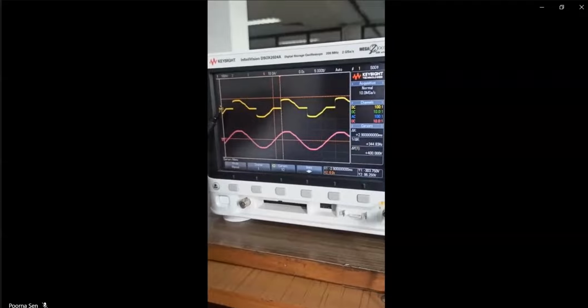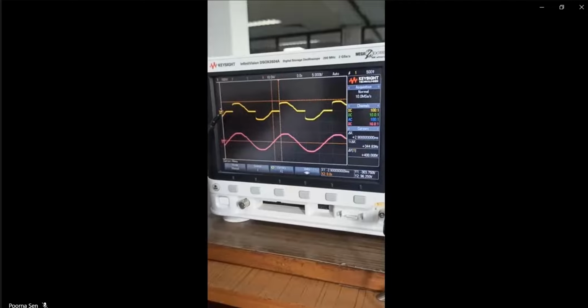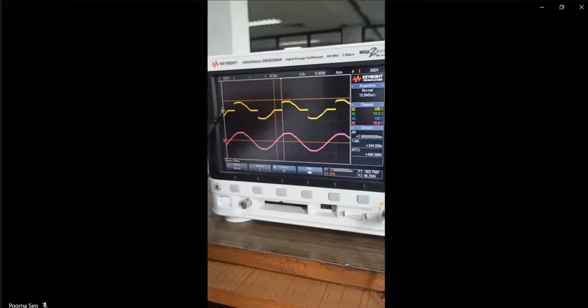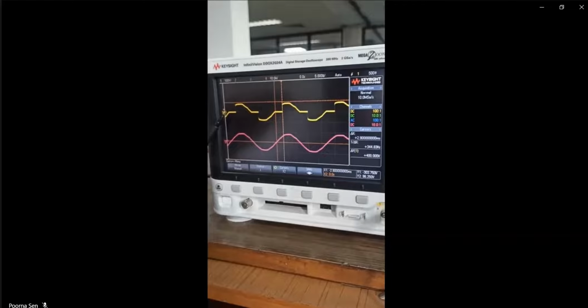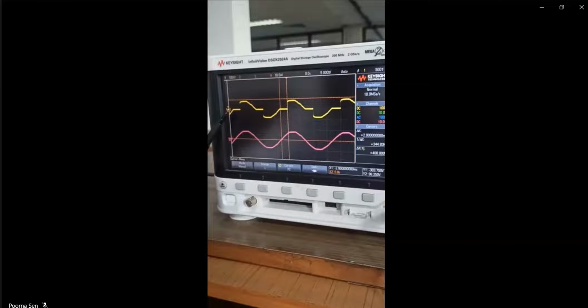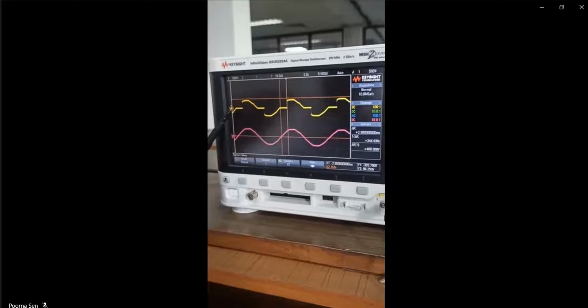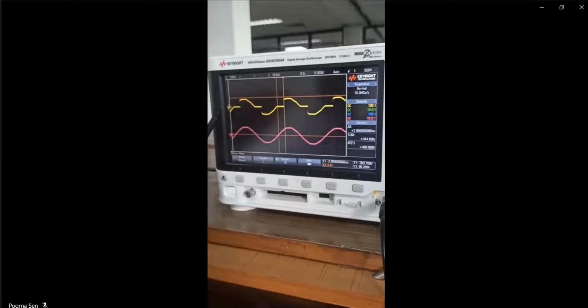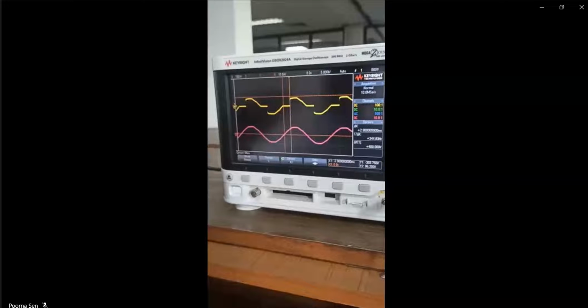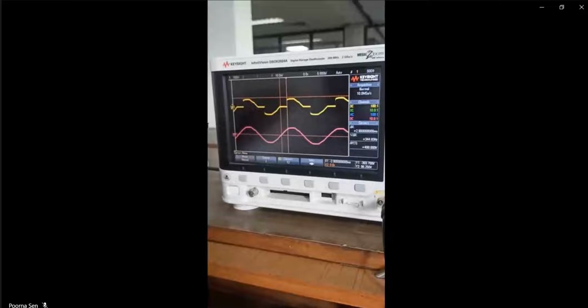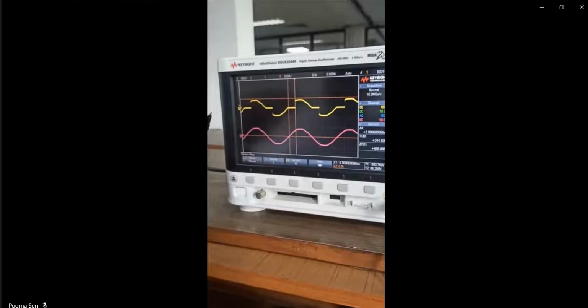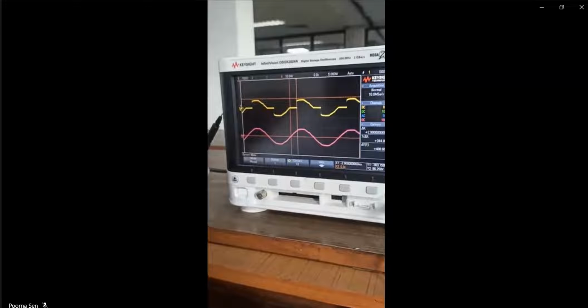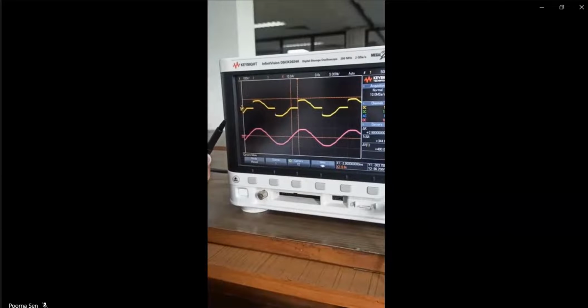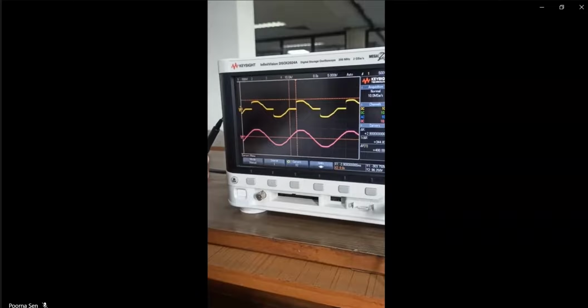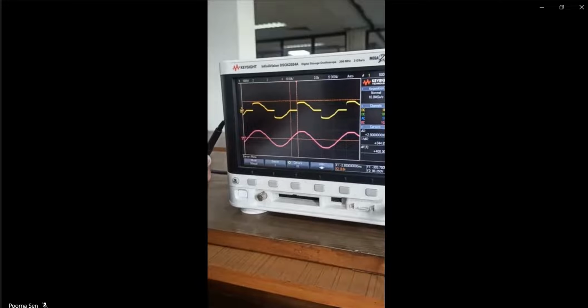So at this moment the firing angle is close to 45 degrees or a little over 45 degrees, and the AC supply is 50 hertz. One cycle time is 20 milliseconds, and half cycle time is 10 milliseconds. So here we can adjust the firing angle anywhere between 0 and 10 milliseconds.